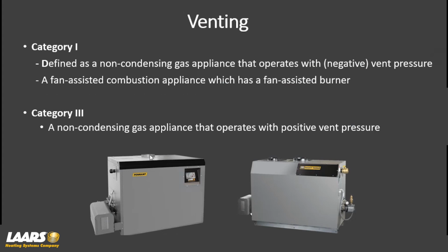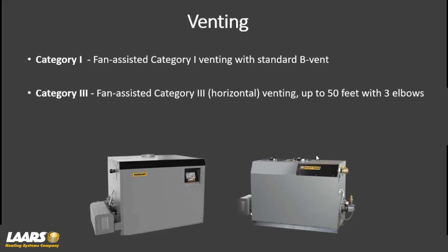Now the venting on these, and I mentioned that the Pennant can be either vented off the top or the rear. MightyTherm2 is currently off the top only. There are 2 categories for venting for this product. We have Category 1, and that's defined as a non-condensing gas appliance that operates with a negative vent pressure. So basically, we'll call that vertical venting. We'll talk about the vent material that can be used. Category 3 is sidewall venting. That is a non-condensing appliance that operates with a positive vent pressure because we have a fan.